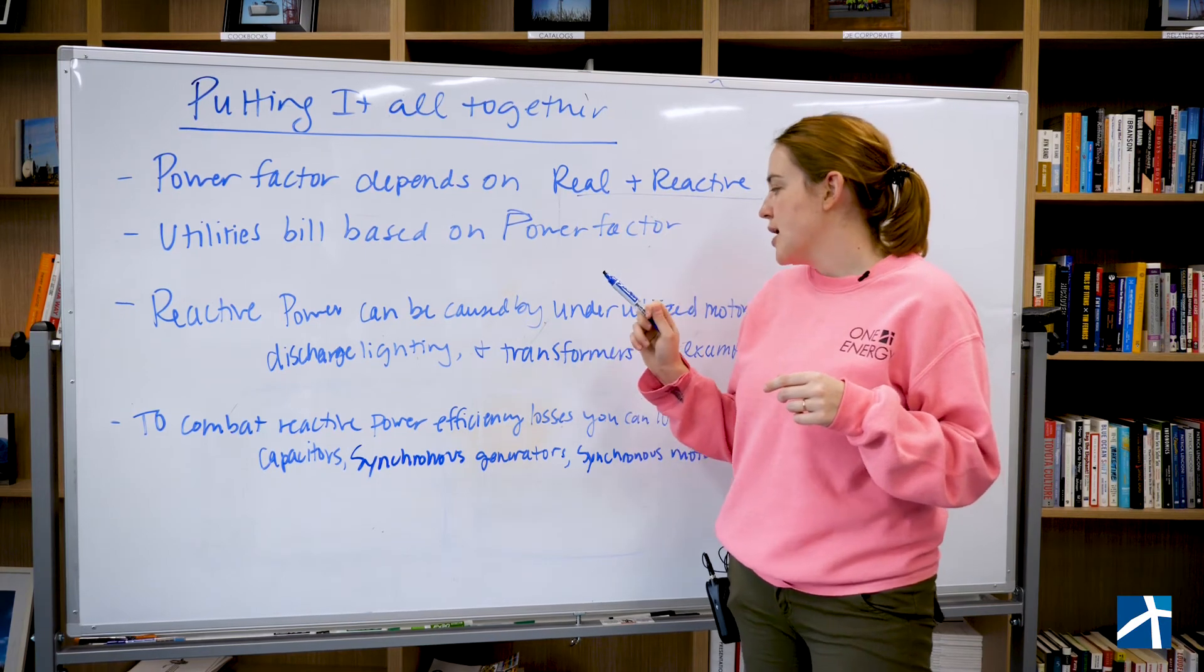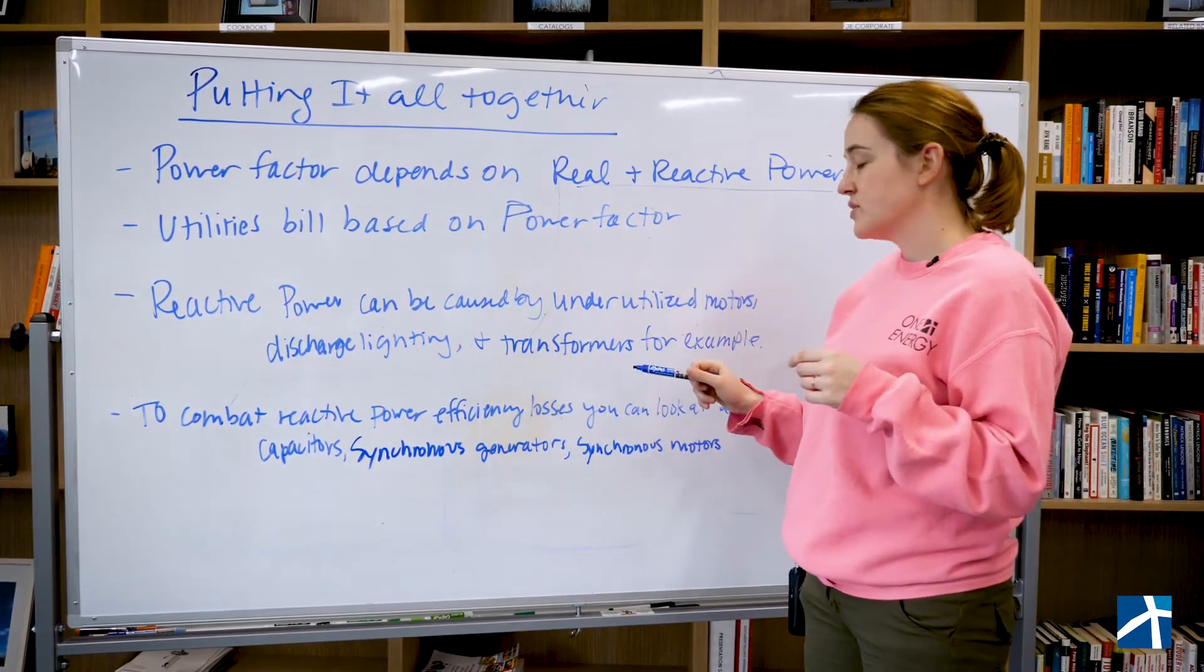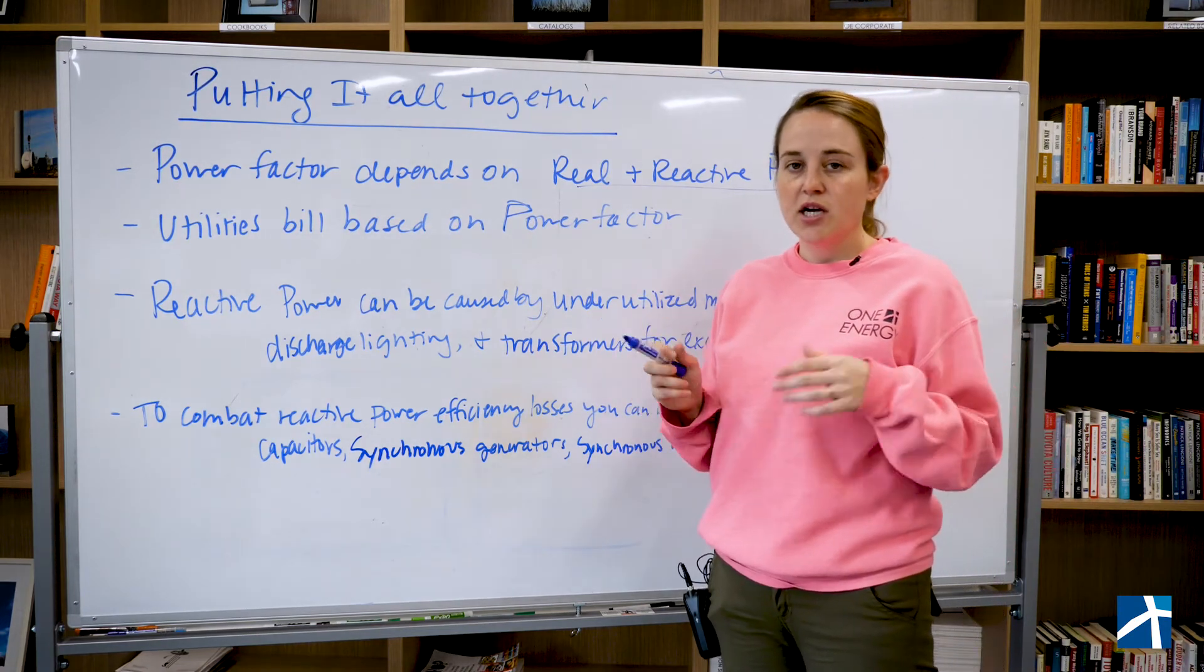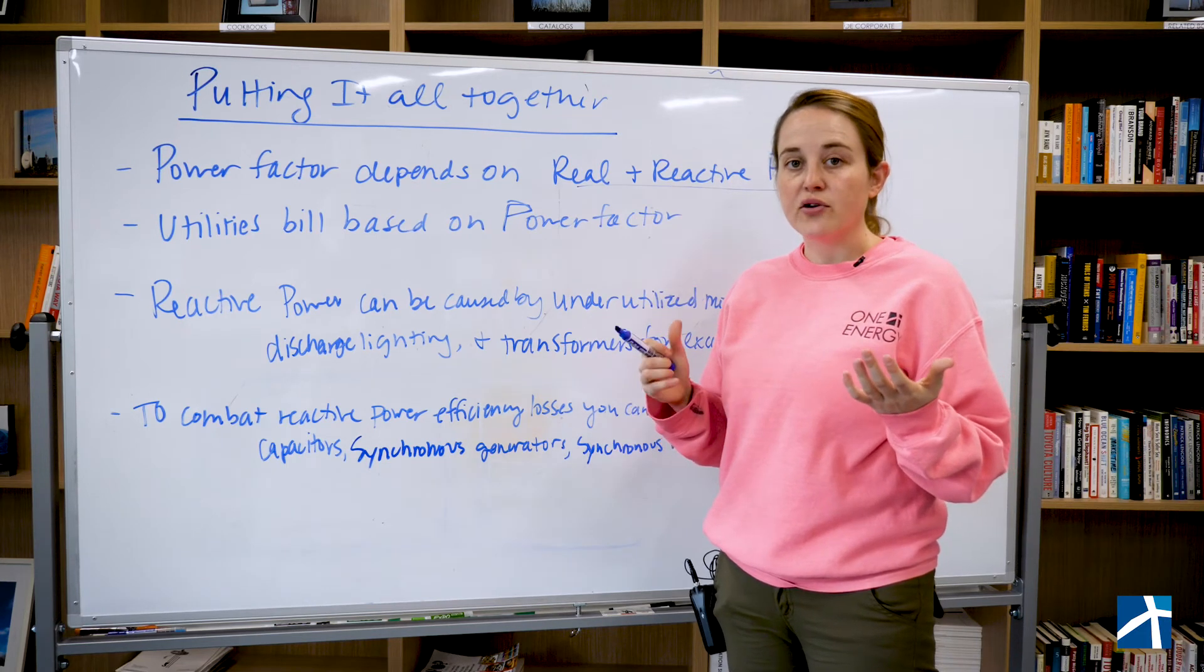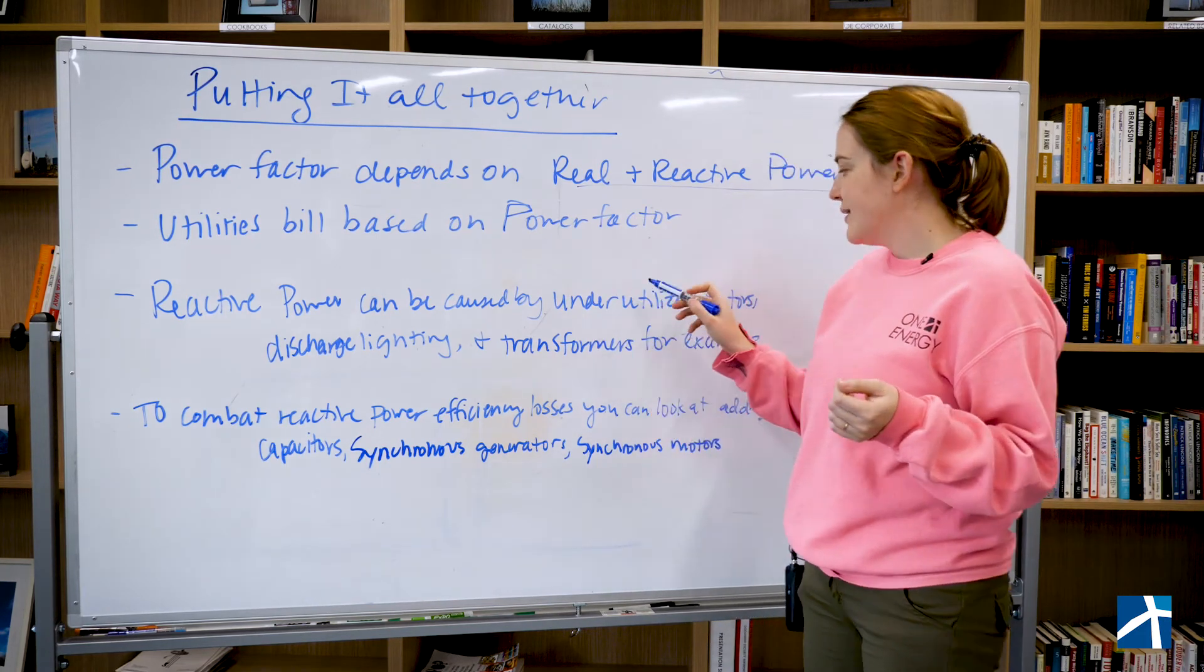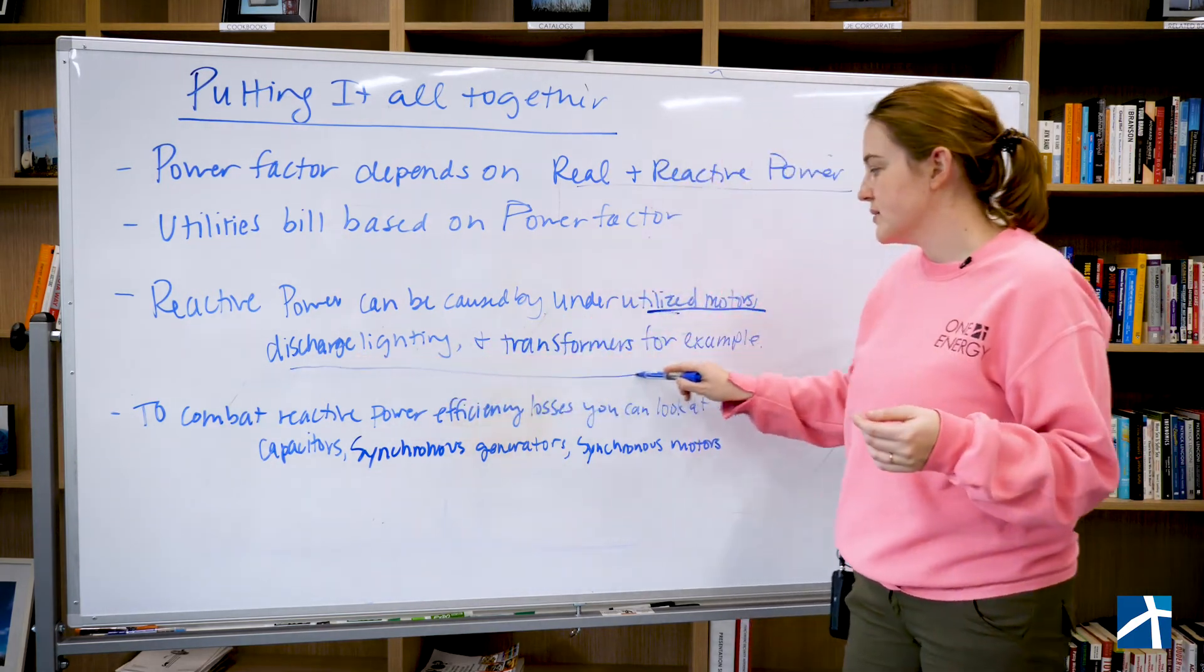Reactive power can be caused by underutilized motors, discharge lighting, transformers. These are all just good examples. So if you are managing energy at a plant or trying to find ways to increase your efficiency, look at these, analyze these things if you have any of them in the system.